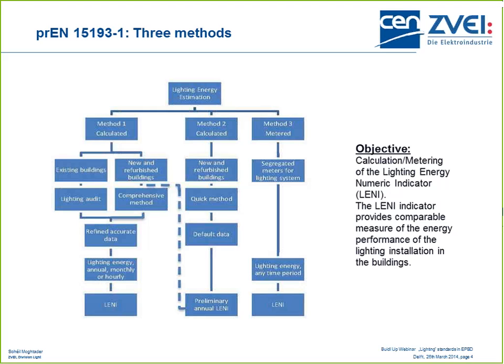And based on this method 2, we will have method 1, which is a calculated method and which will be much more detailed. And the idea there is that it is very important not only making the estimation, but also having a lighting design process incorporated in this method, so that you can know which zone you have, which type of visual task, and what type of luminaires and illumination is needed.